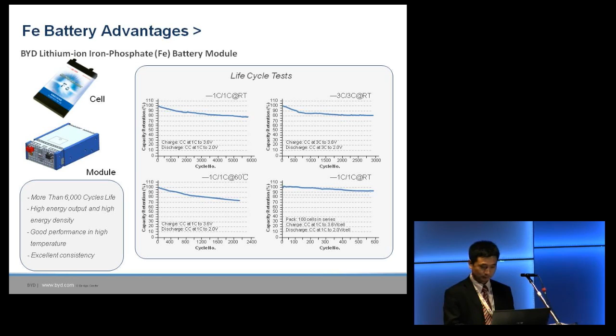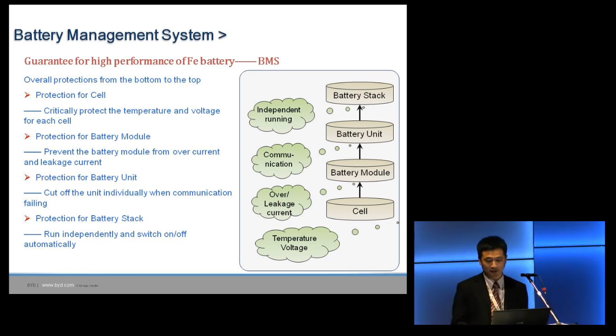The BMS system is very key for the whole system, which is why we recommend customers and partners use the vertical integration solution to manage it. Looking at the picture, from bottom to top, the BMS offers four levels of protection for these batteries: at the cell level, it protects temperature and voltage; at the battery module level, it protects against over-leakage and over-current; at the battery unit level, if communication to the whole system fails, it can cut off directly and run independently; and the battery stack can also run independently through this BMS protection.